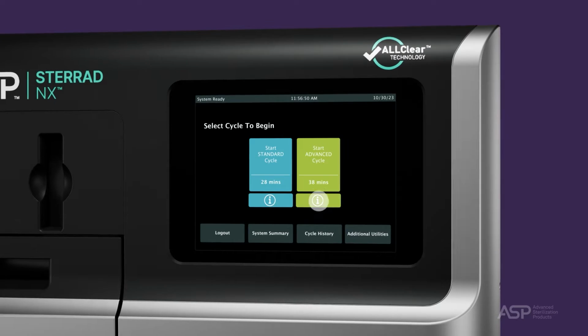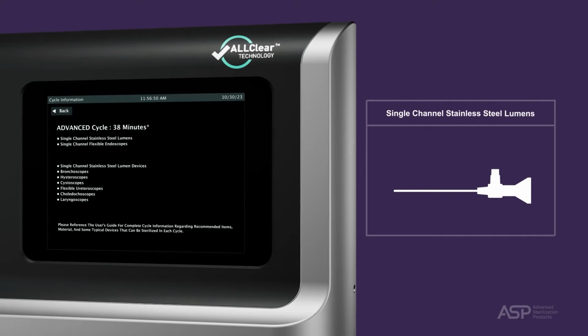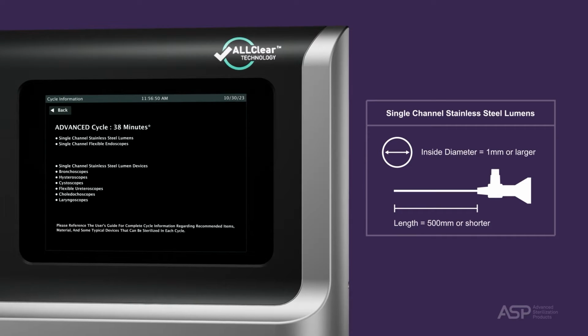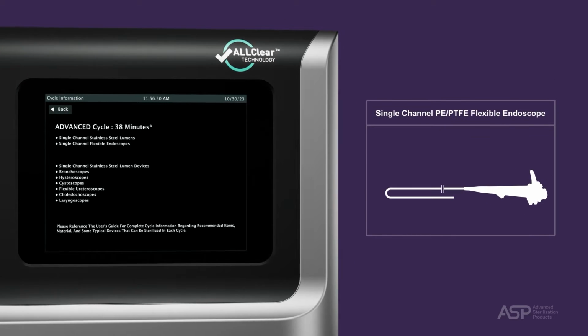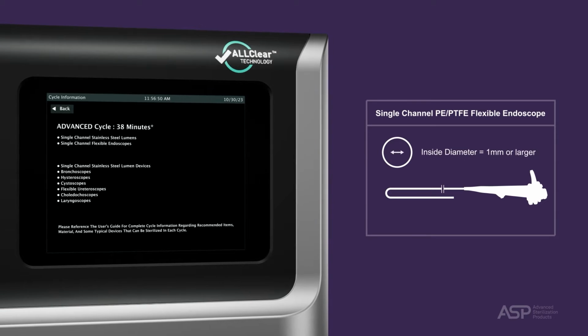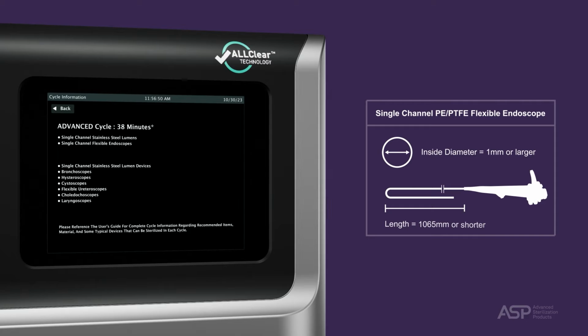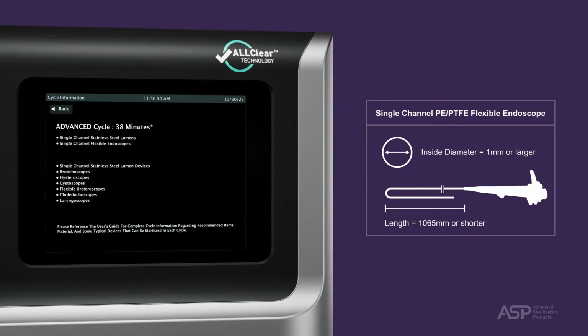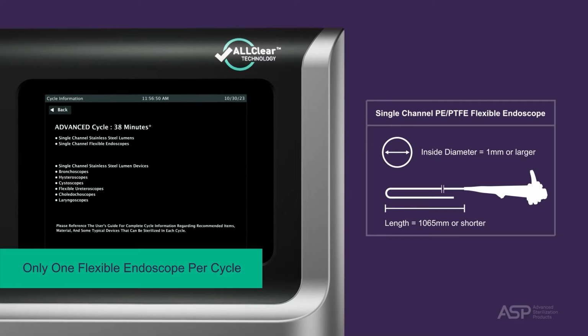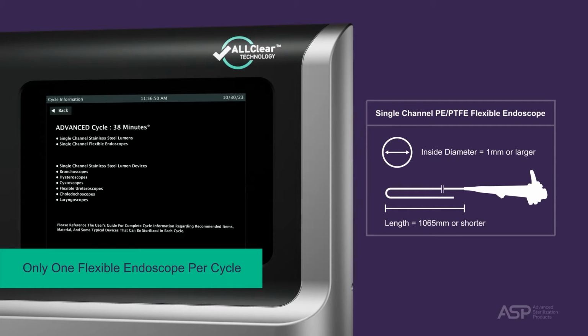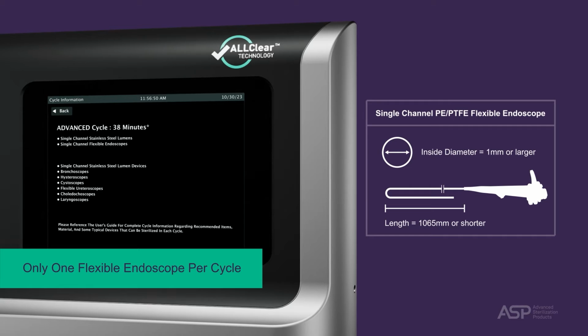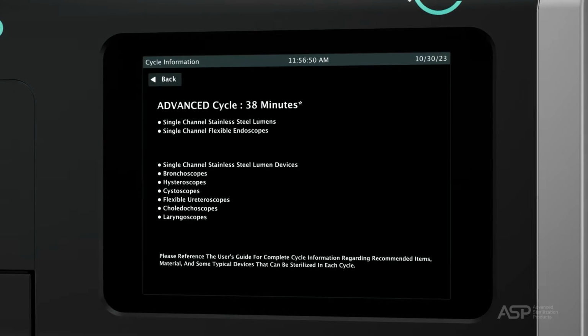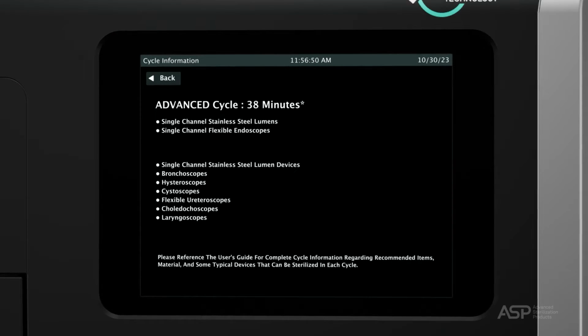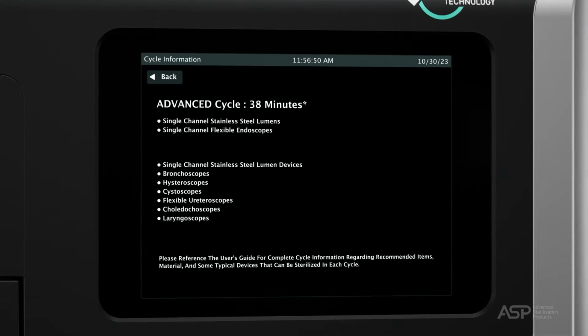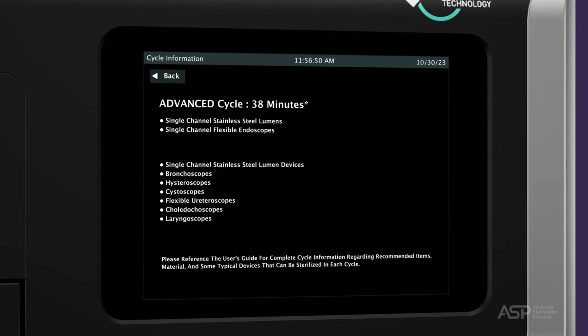The advanced cycle is 38 minutes and should be selected for single-channel stainless steel lumens with an inside diameter of 1 mm or larger and a length of 500 mm or shorter, and single-channel PE/PTFE flexible endoscopes with an inside diameter of 1 mm or larger and a length of 1,065 mm or shorter. Only one flexible endoscope may be sterilized per cycle with or without a silicone mat, and no additional load items may be included in that cycle. Typical single-channel flexible endoscopes would include bronchoscopes, hysteroscopes, cystoscopes, flexible ureteroscopes, choledochoscopes, and laryngoscopes.